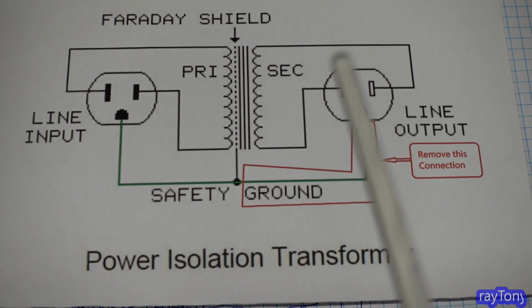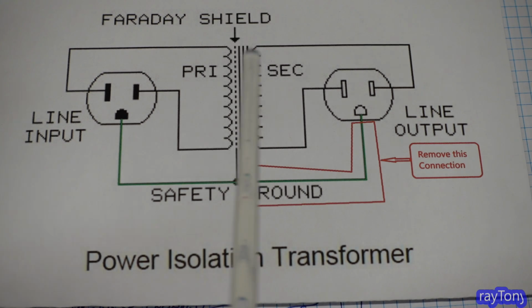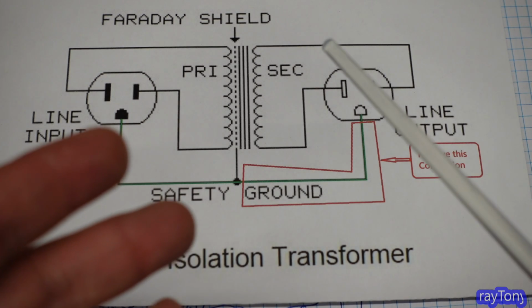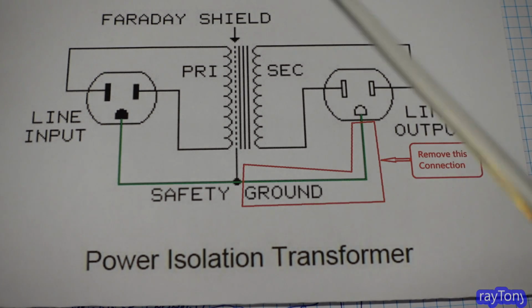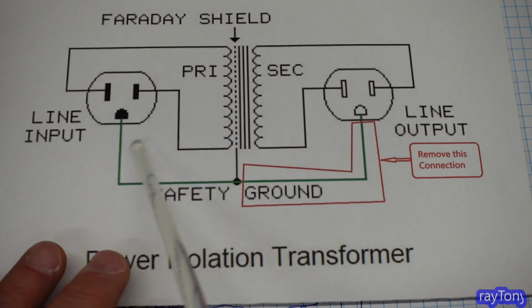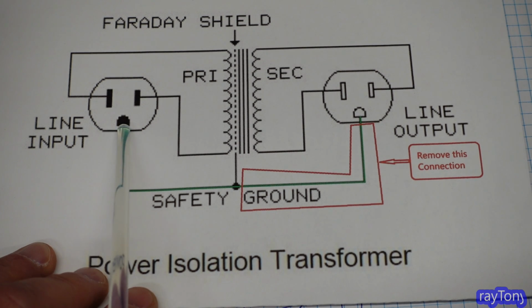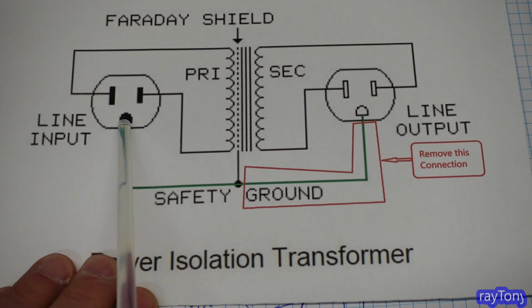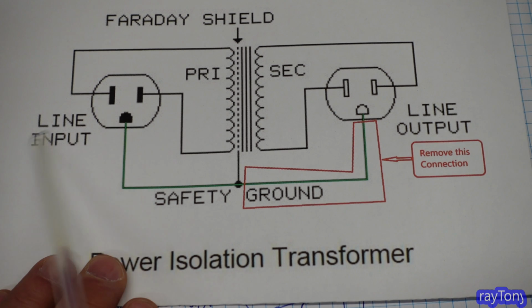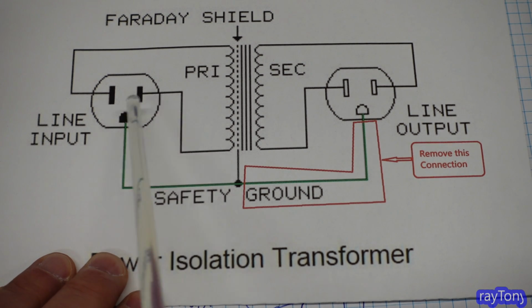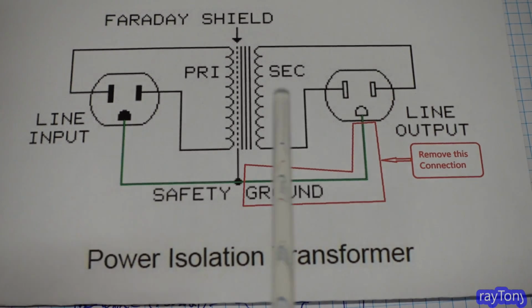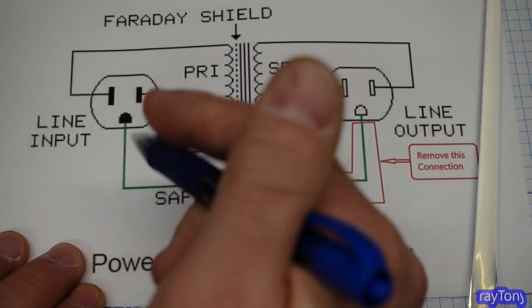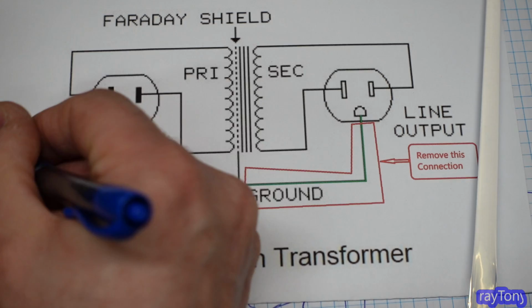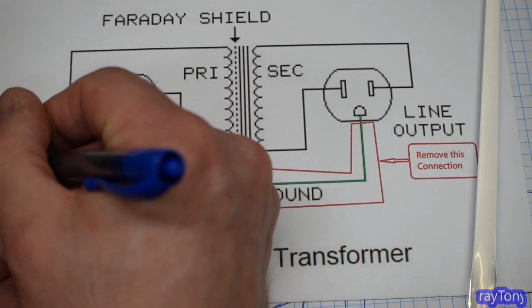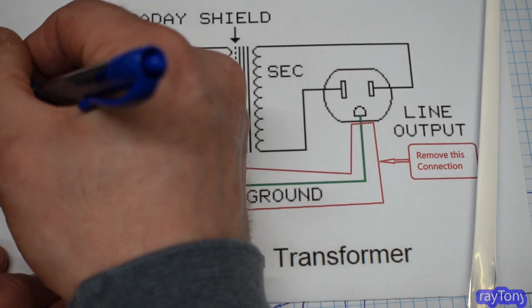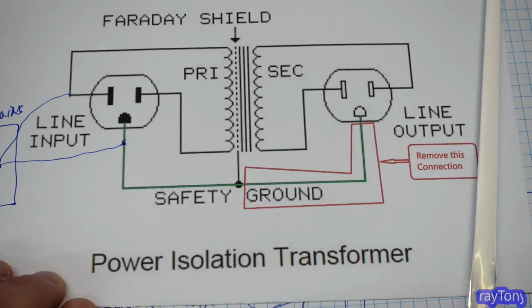But because of the electrical code, especially if you buy a hospital grade isolation transformer—you'd figure hospital grade means higher quality—well, no. What they do is take this ground prong, which goes to the ground in your power box, which by the way is bonded to the neutral. So technically, in your power box, this and this are tied together.